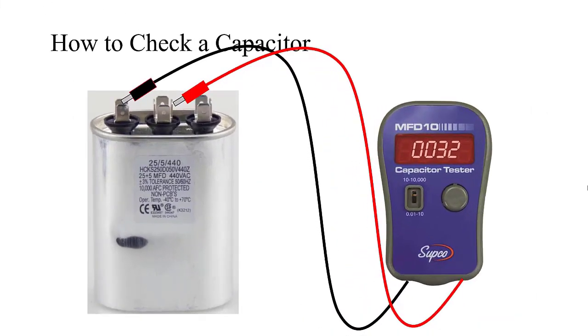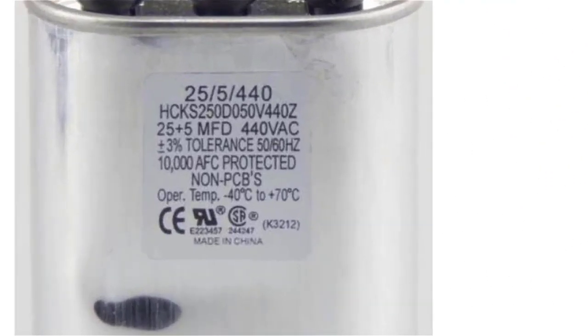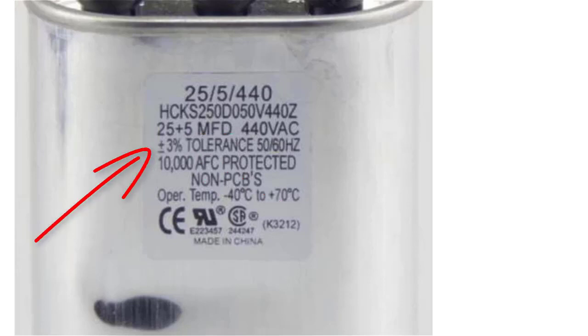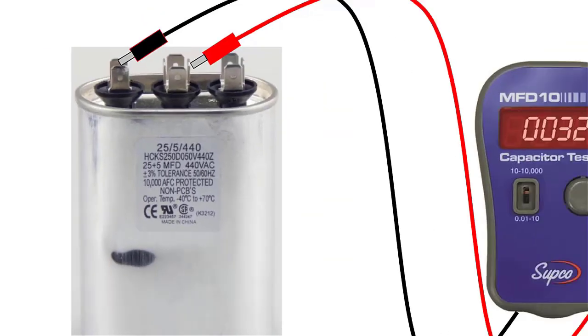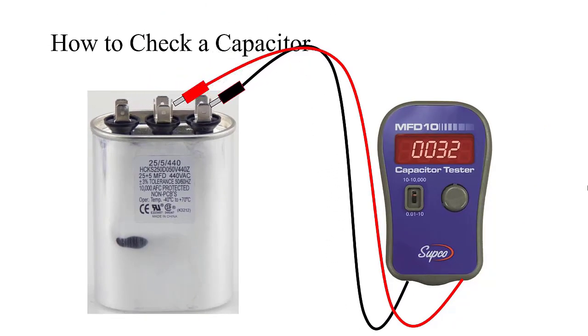Most new multimeters will check the capacitance of a capacitor, or you can use a capacitance tester. Let's take a closer look at this capacitor. It is a dual run — 25 microfarads to the compressor and 5 microfarads to the outdoor fan motor. Notice it has a tolerance of only 3% either way. In other words, it needs to measure 25 and 5 or it is bad.